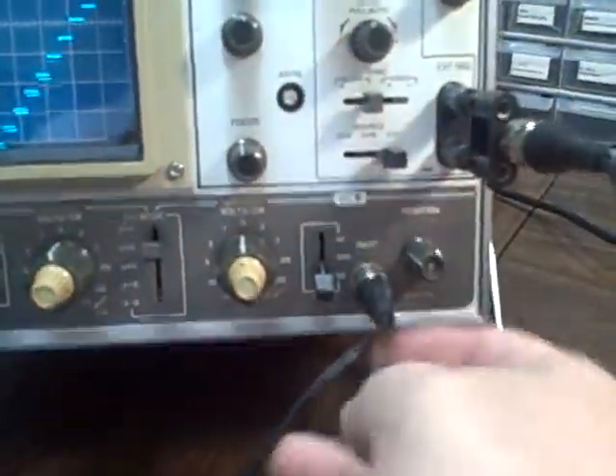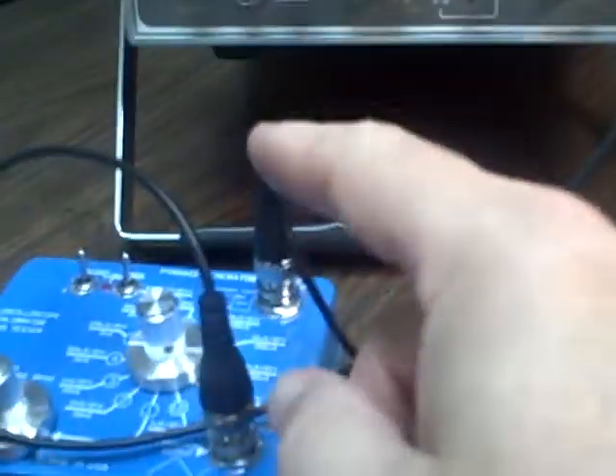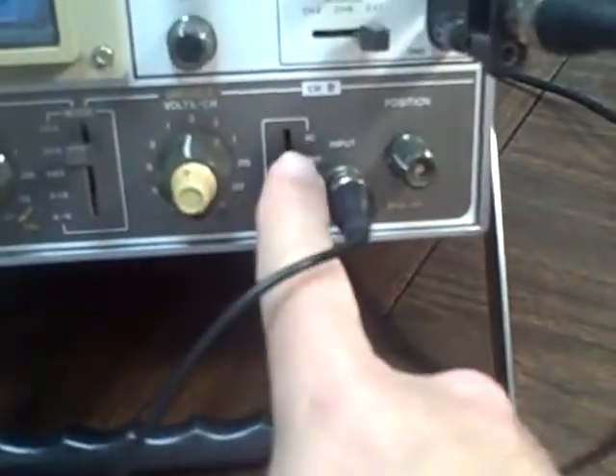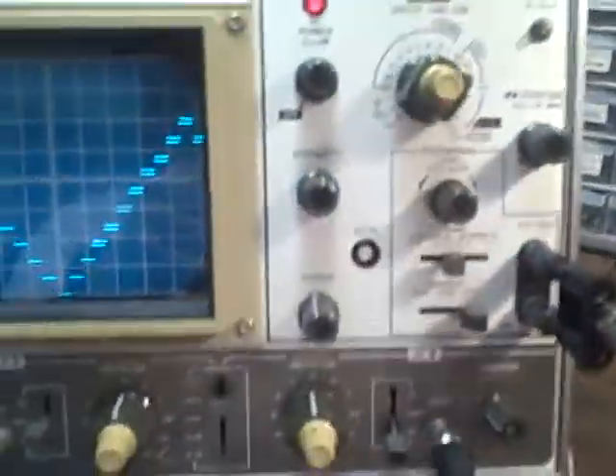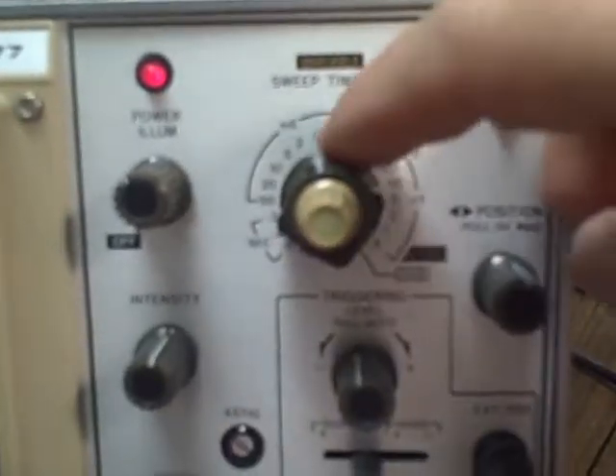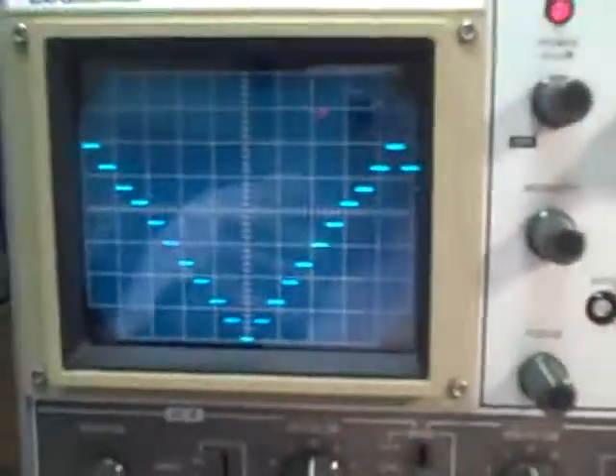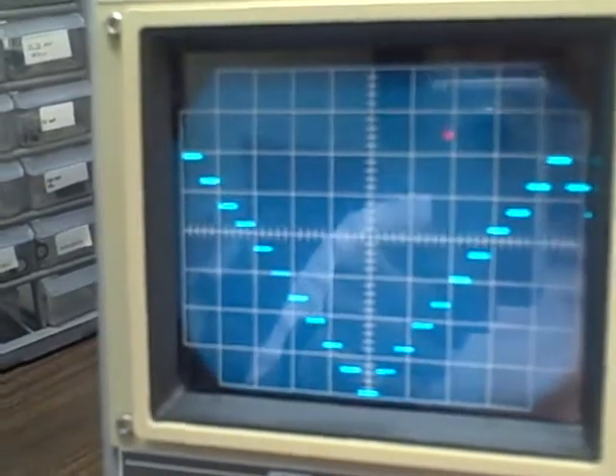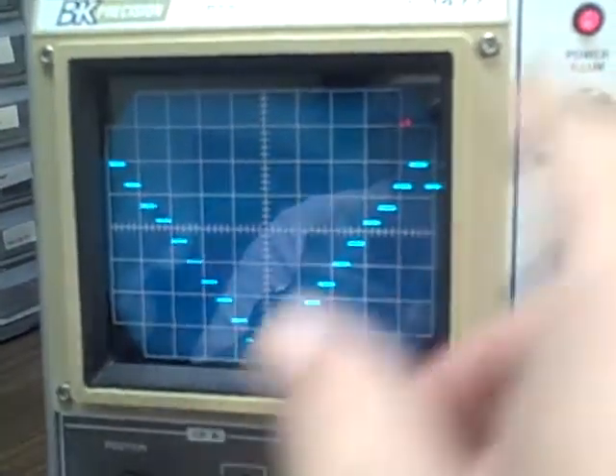As you can see, we have now switched our calibrator's output to channel B, and we are in the DC position on channel B. We are external triggering once again. We are at one millisecond per division on the scale, and we see the somewhat familiar by now 10 stair steps down and up again.